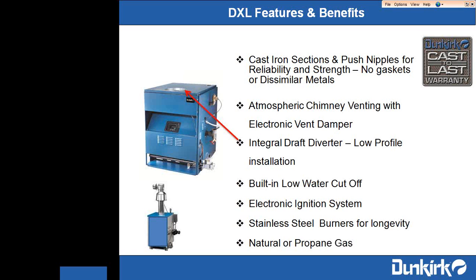Again, it's an atmospherically vented boiler, but what's nice about it is we have a built-in draft diverter. If you look at the picture of the boiler at the bottom of the screen, you'll see companies like Burnham, Slantfin, Weil-McLain, Buderus. They all require an external draft hood. It adds about 12 to 18 inches to the installation height of the boiler. And if you're looking at older homes that have low basements, sometimes those boilers will not fit in that installation. So you have a built-in draft diverter on the DXL. The only thing the contractor has to account for is the vent damper that comes with the boiler, and then he puts his smoke pipe right on top of the vent damper. All gas boilers now have to be electronic ignition. There are no more standing pilot boilers.